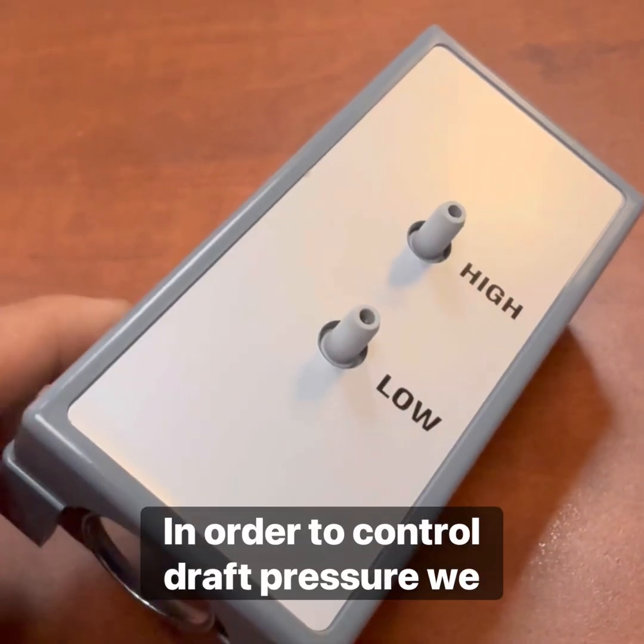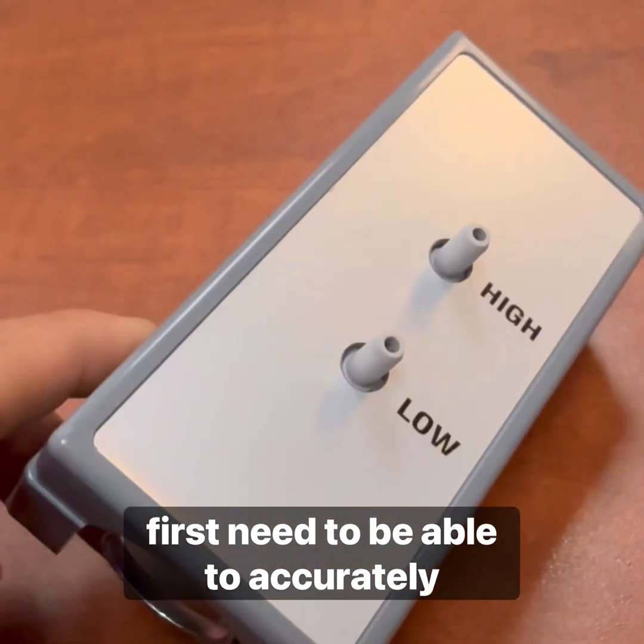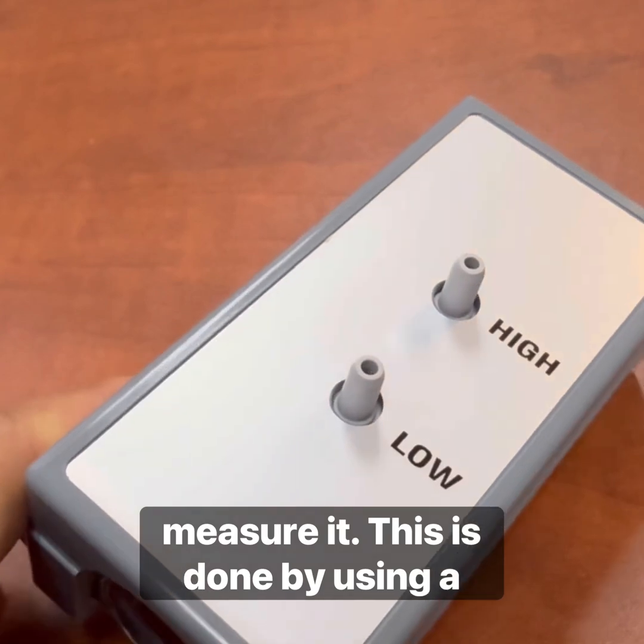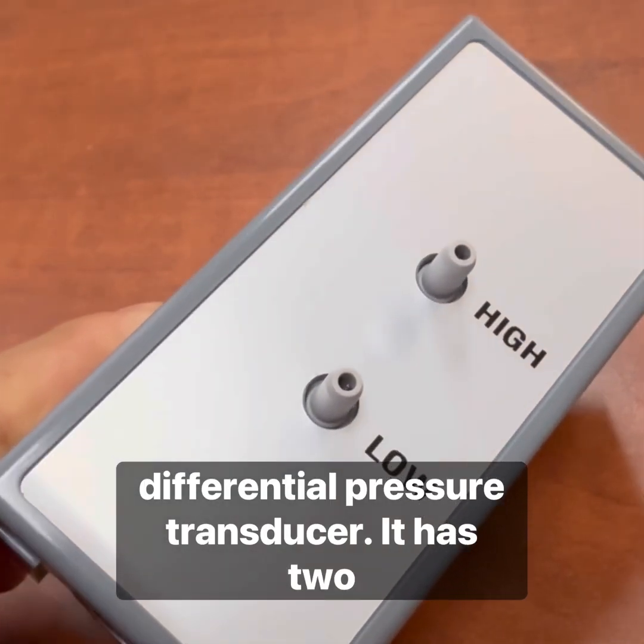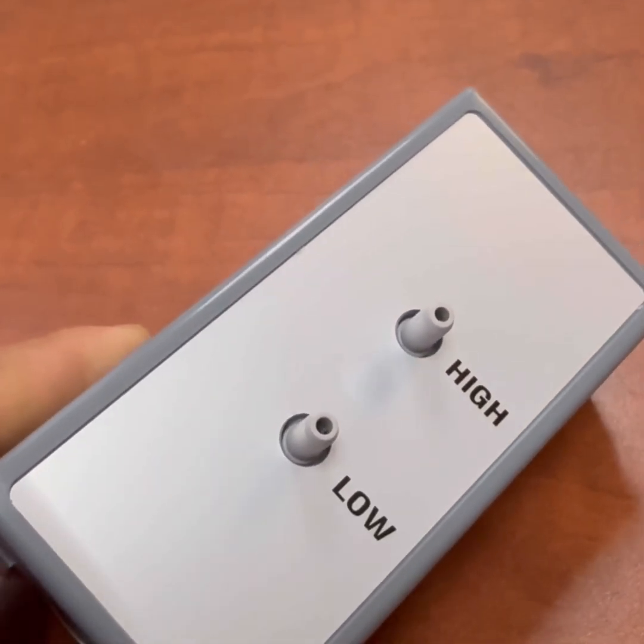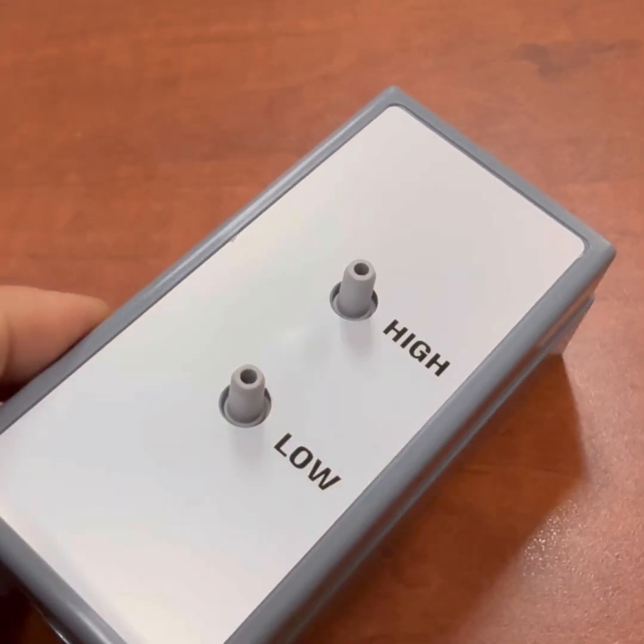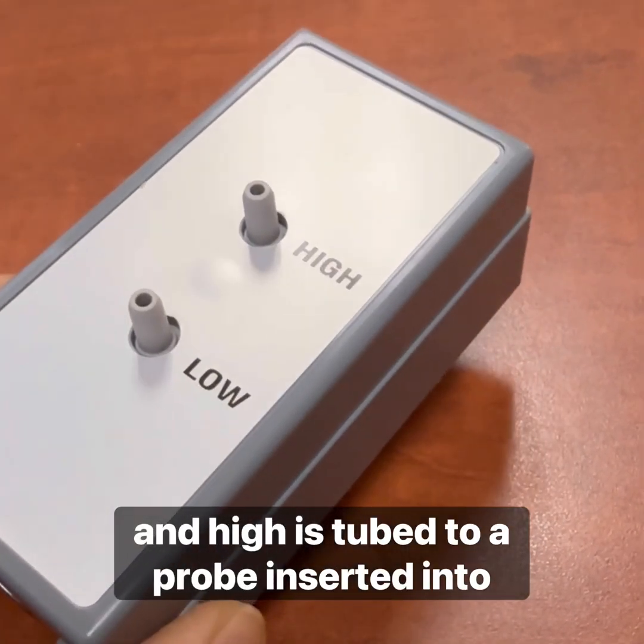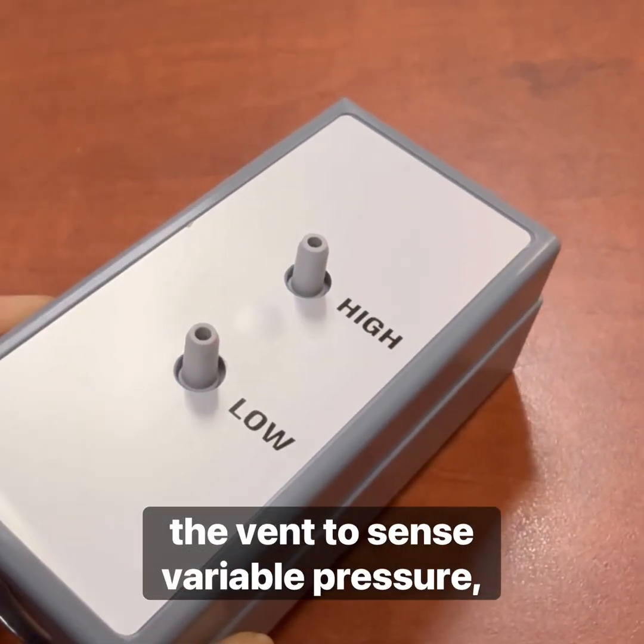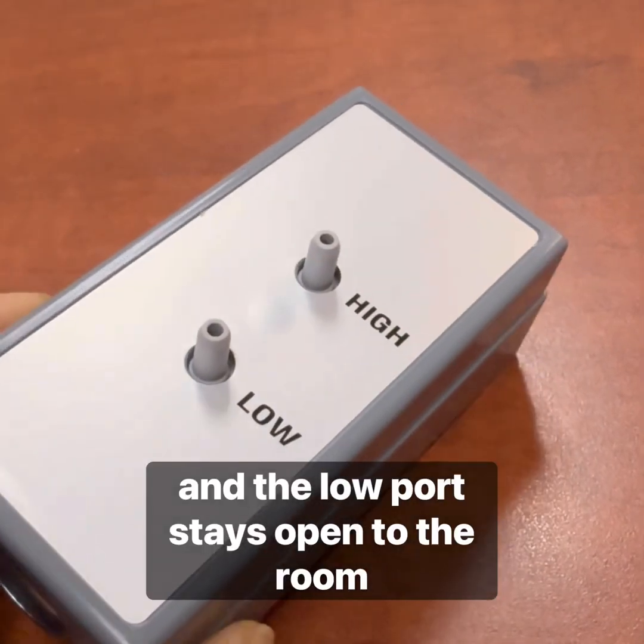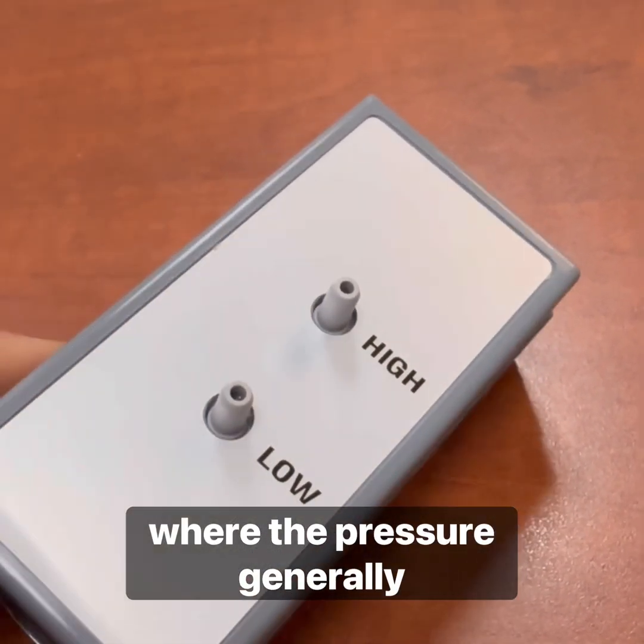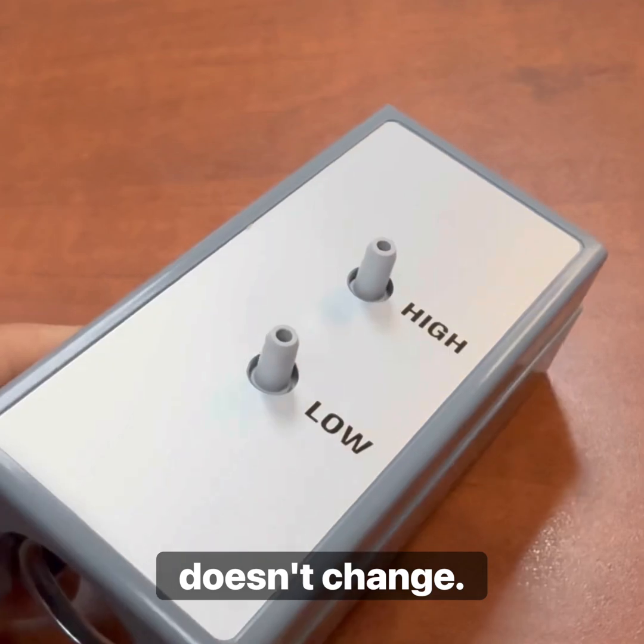In order to control draft pressure, we first need to be able to accurately measure it. This is done by using a differential pressure transducer. It has two ports, a high and a low, and high is tubed to a probe inserted into the vent to sense variable pressure, and the low port stays open to the room where the pressure generally doesn't change.